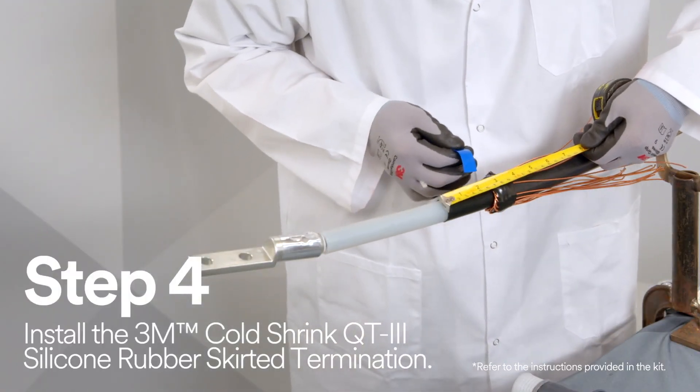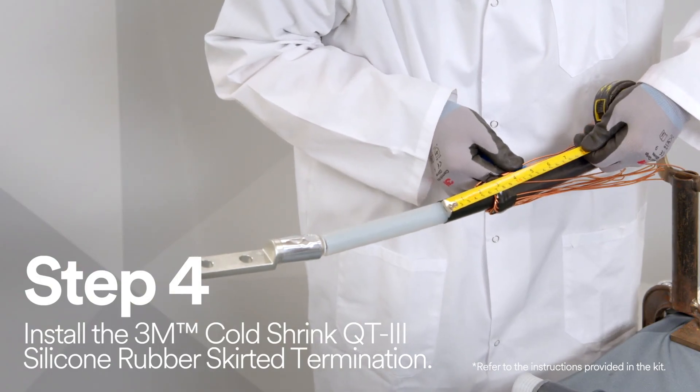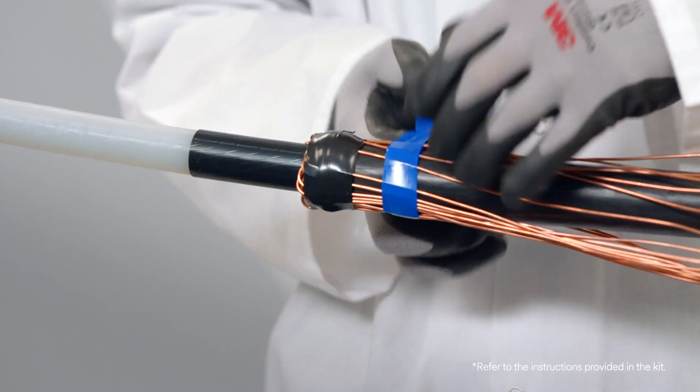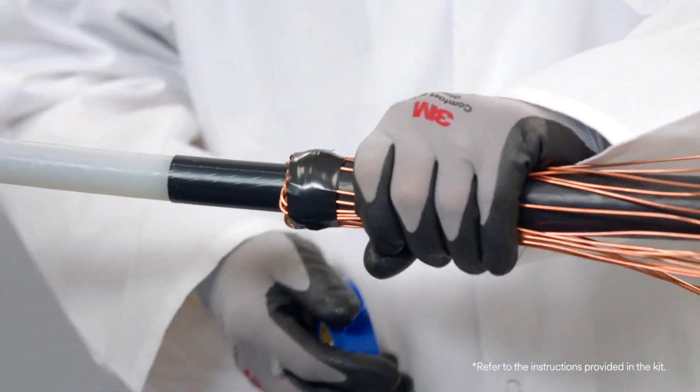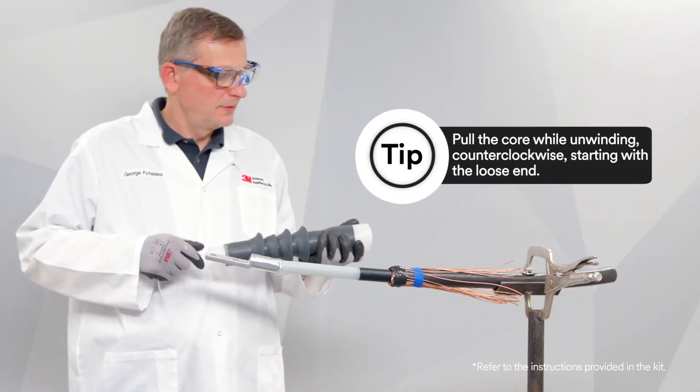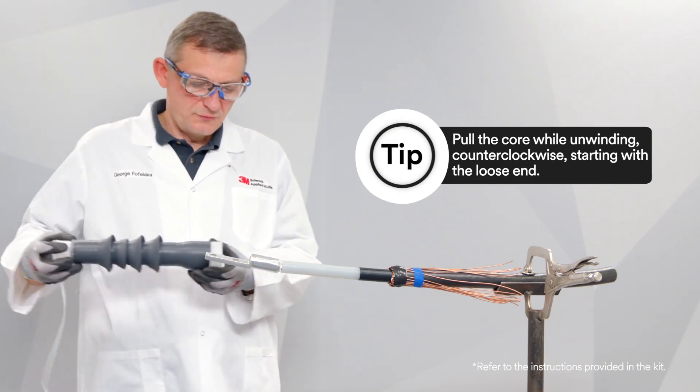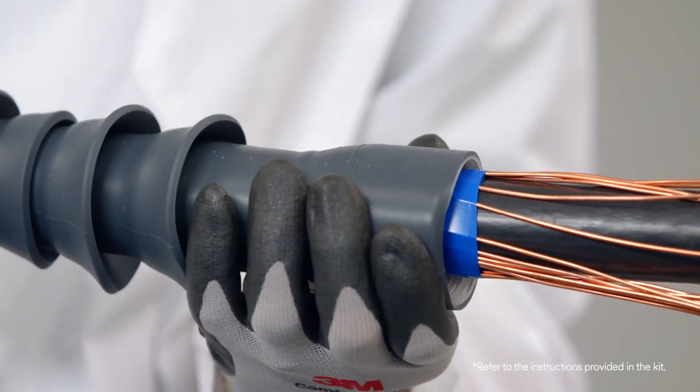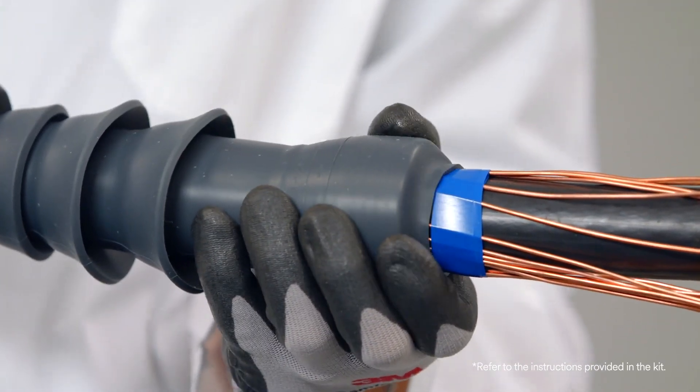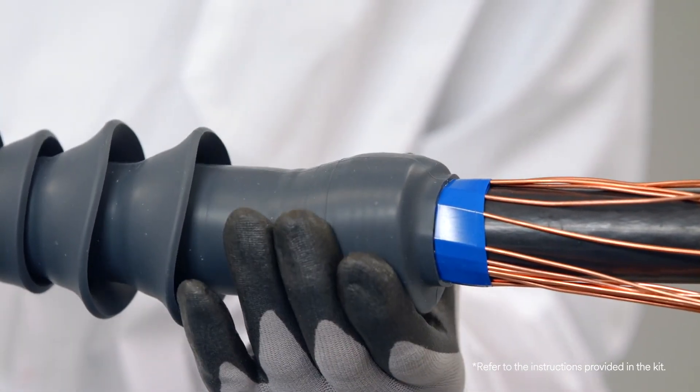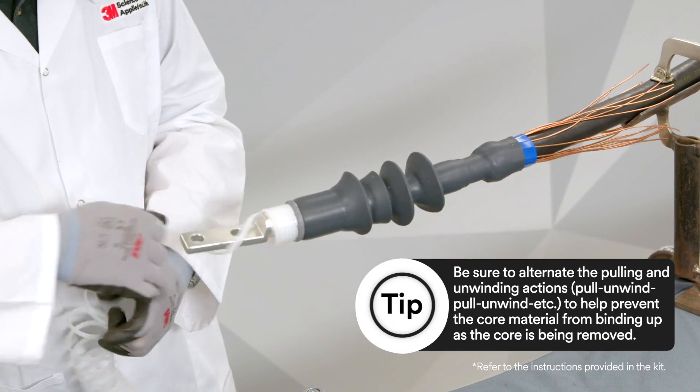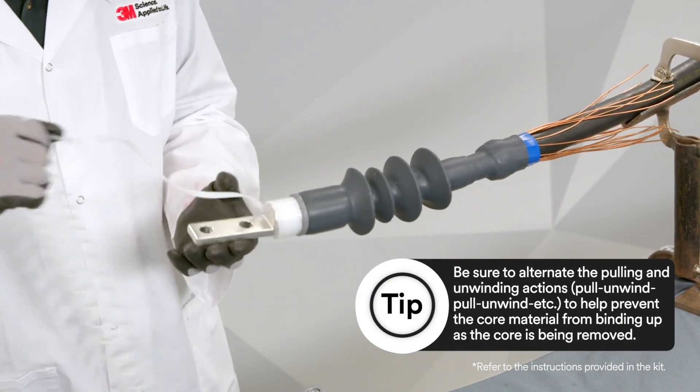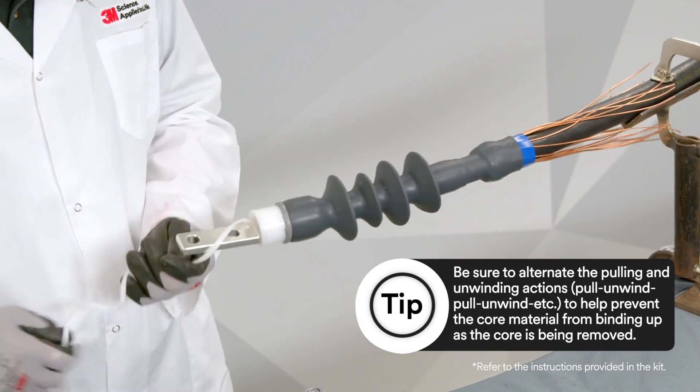First start by adding marker tape. Secure Scotch vinyl color coding electrical tape 35 to the cable jacket 4.5 inches from the cable semi-con edge. Then slide the termination body onto the cable so it aligns to the edge of the marker tape and remove the core. Make sure the termination body, not the core, is right at the edge of your marker tape.